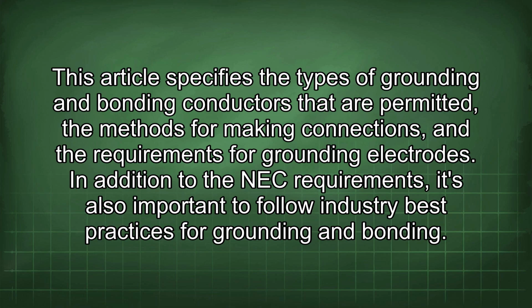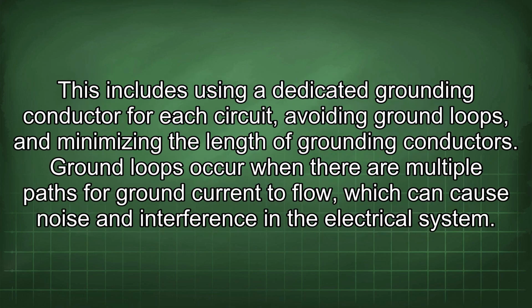requirements for grounding electrodes. In addition to the NEC requirements, it's also important to follow industry best practices for grounding and bonding. This includes using a dedicated grounding conductor for each circuit, avoiding ground loops, and minimizing the length of grounding conductors. Ground loops occur when there are multiple paths for ground current to flow, which can cause noise and interference in the electrical system.